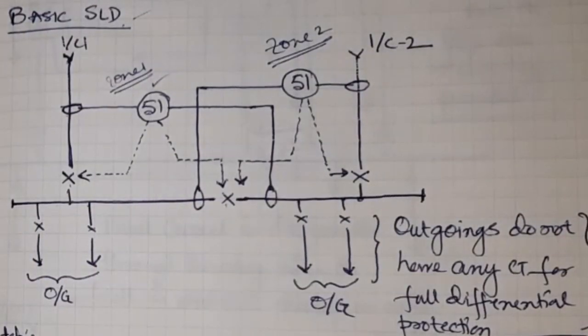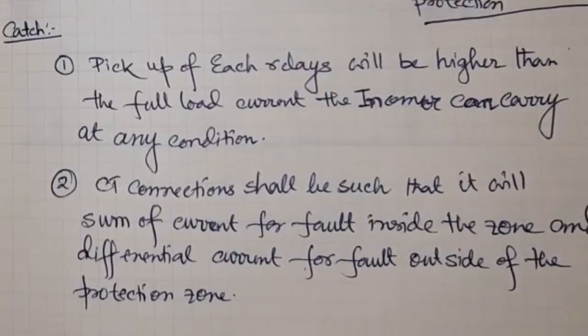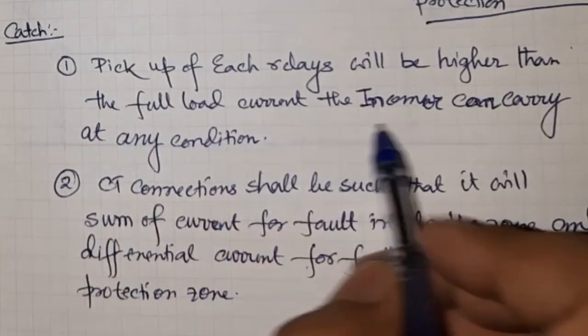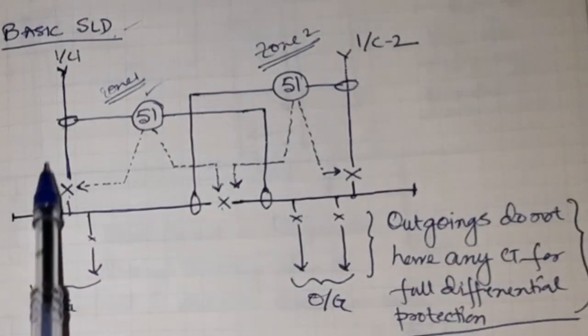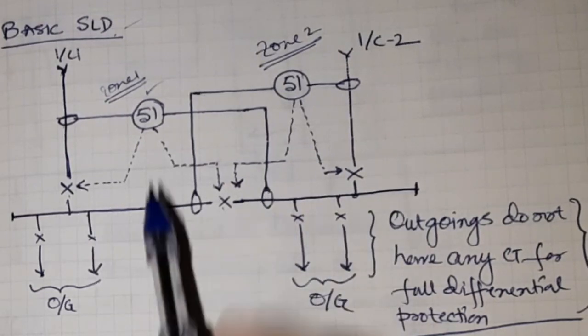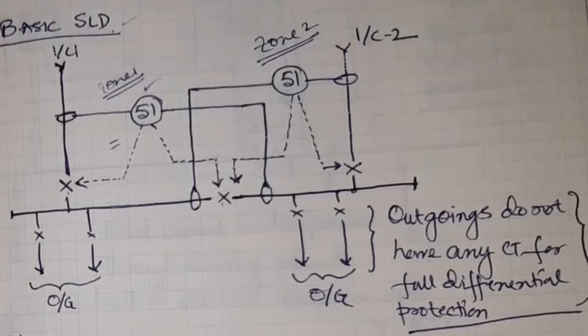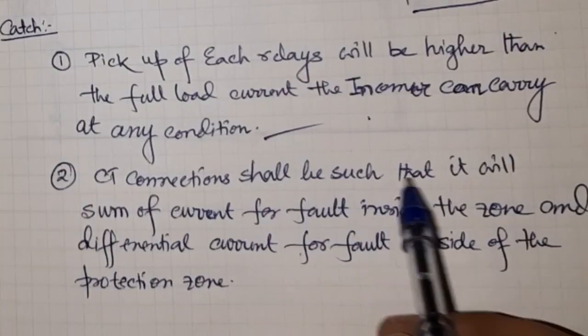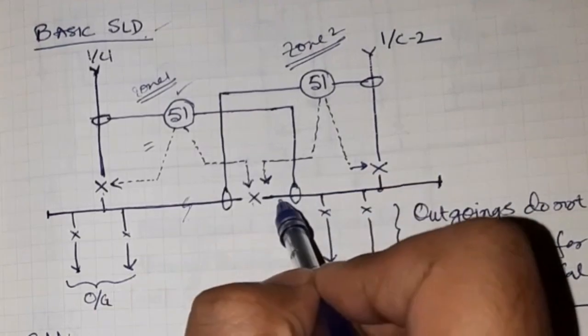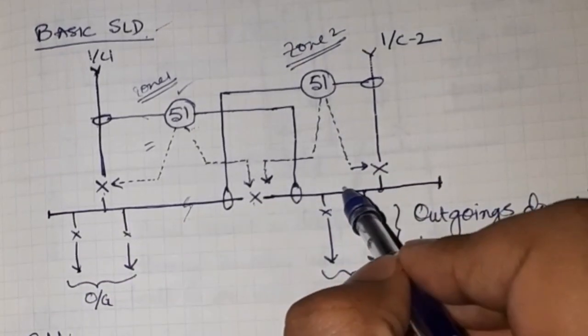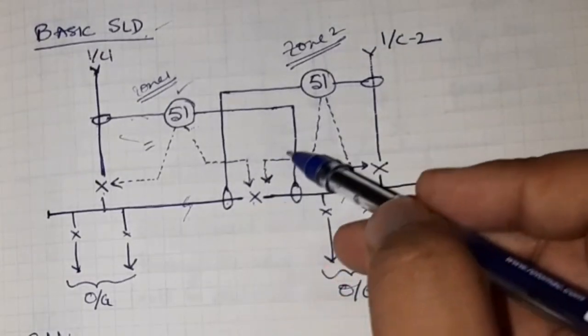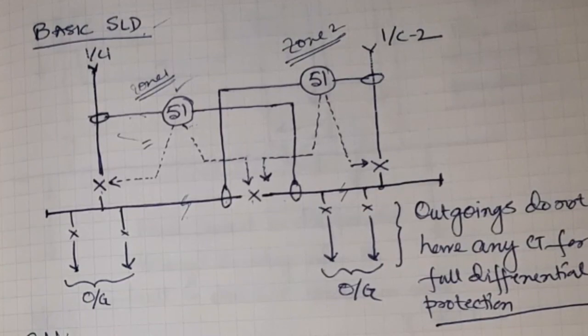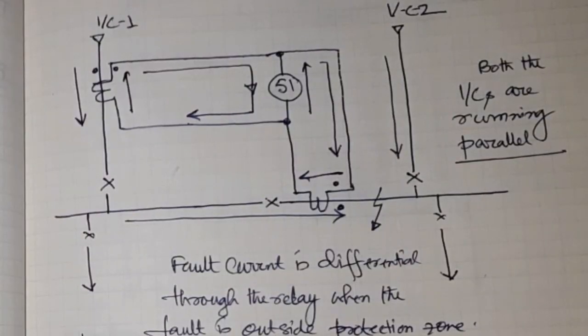There are two key catch points. Number one: the pickup of each relay shall be higher than the full load current the incomer can carry under any condition — whether the incomers are running in parallel or one incomer is carrying the full bus load. Number two: the CT connection shall be such that it gives a summation of current for a fault inside the zone. If there is any fault outside the zone, the two CTs will give a differential current, and for a fault inside the zone, the two CTs will give a summation of current.